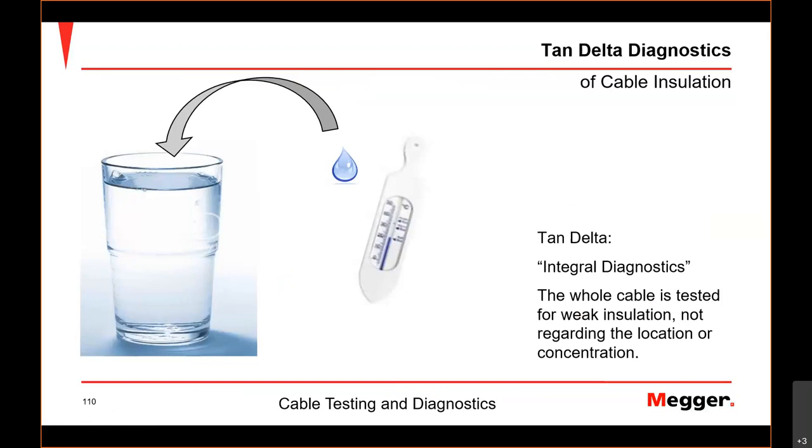That's why it would make sense, after the tan delta value, to do a VLF cable test, very low frequency. Imagine you have a long cable with one bad weak spot. Overall, the tan delta will measure and find your cable is in very good condition. This one bad weak spot won't really show up in the overall average.